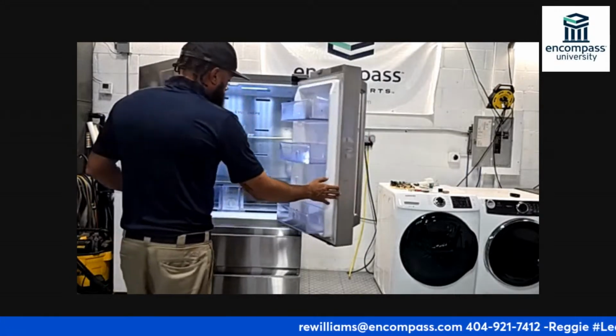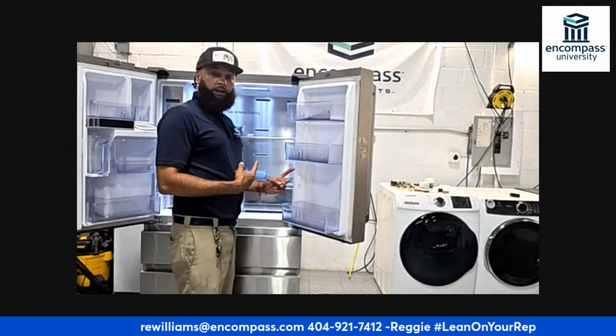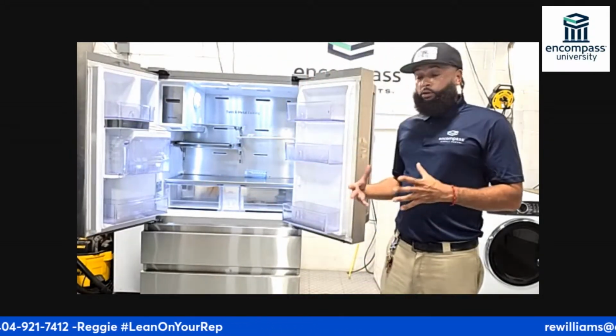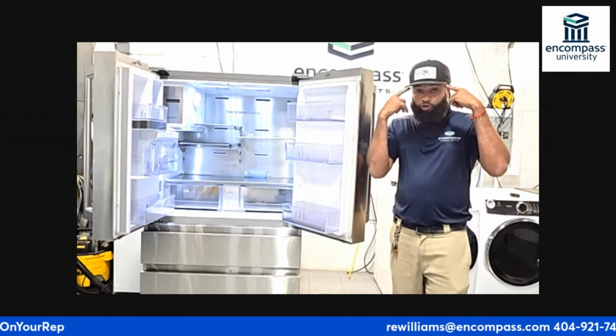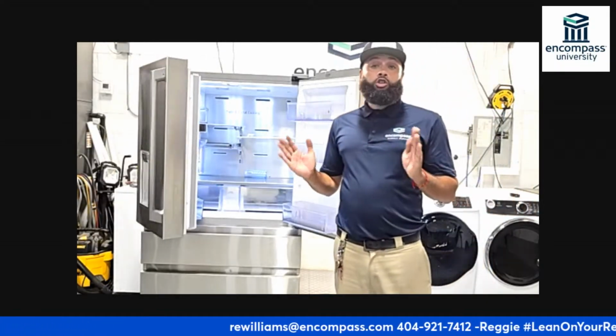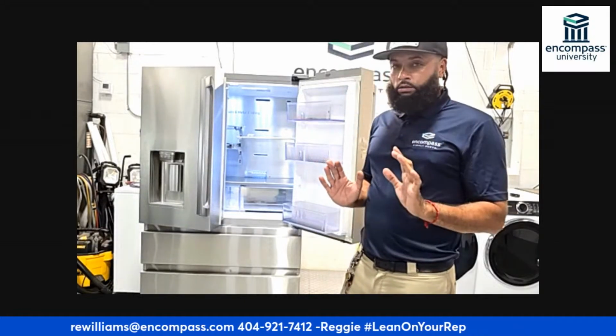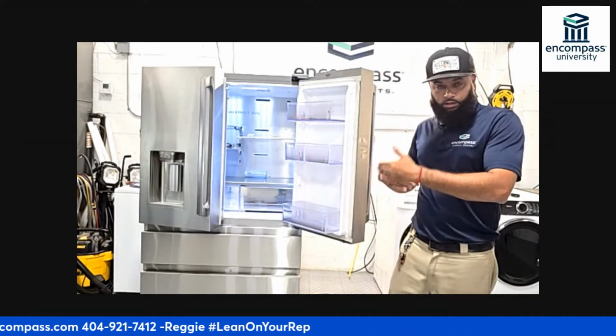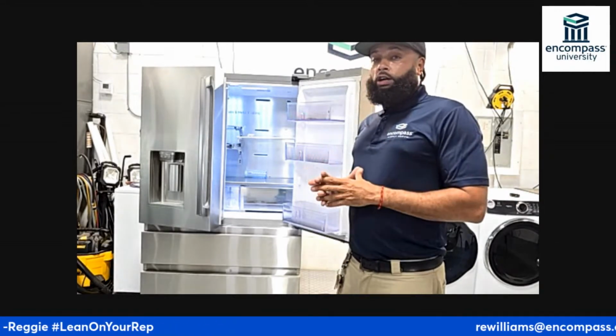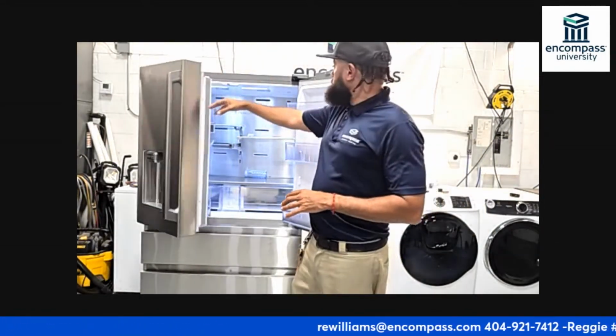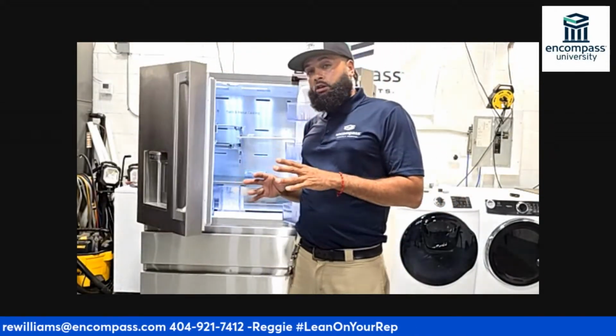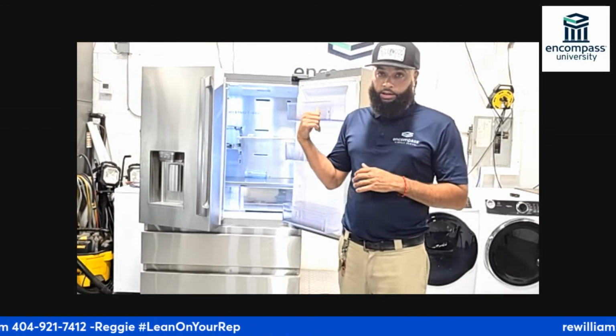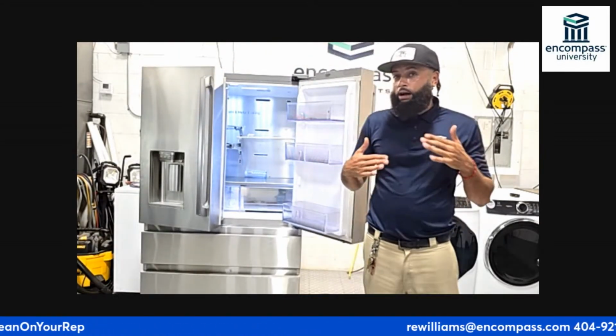First thing we want to listen for when we come to these units is to hear our evaporator fan running. But with these Samsungs and some other manufacturers, the fans won't operate when the doors are open. So we have to trick the computer into thinking the doors are closed, and wait 7 to 12 seconds for the fans to begin working. You'll know you've accomplished this when you hold your door switches and the lights turn off. Once the lights turn off and remain off, you should hear your fans operate. That's the first hearing test I want to perform.